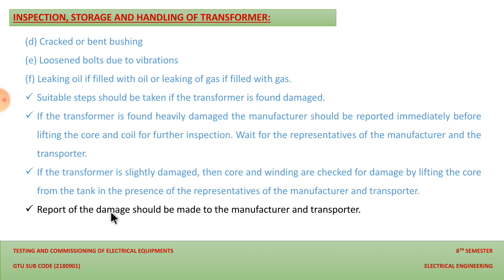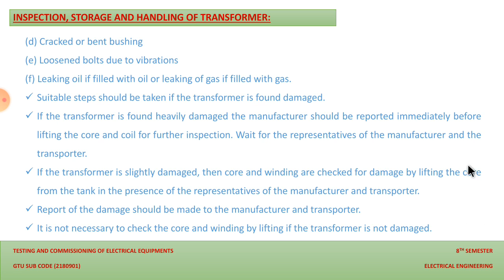It is not necessary to check the core and winding by lifting if the transformer is not damaged. So if the transformer is not damaged, then this step is not necessary. But if it is damaged from the outside, we need to check the core and winding, because if these two are broken, that is the main part of the transformer. So you have to prepare a detailed report of the damage, and you should submit it to the manufacturer and the transporter. So these are the points which you should keep in mind during the inspection.